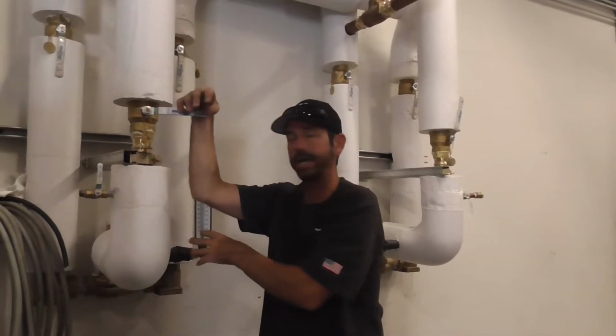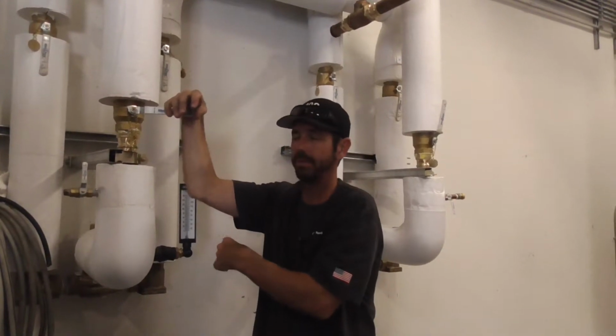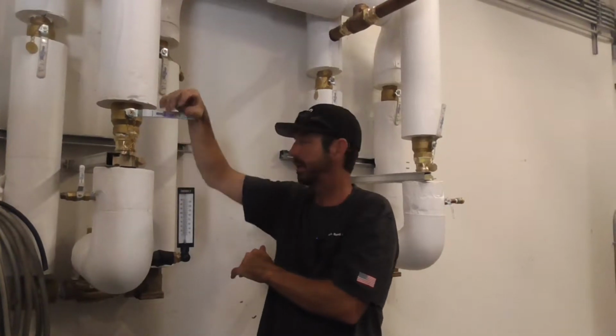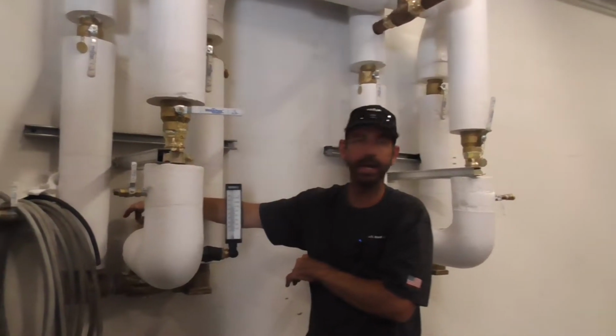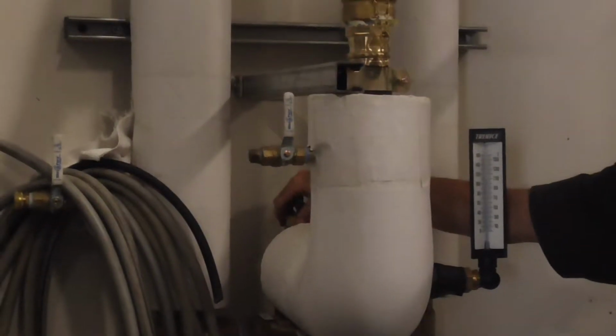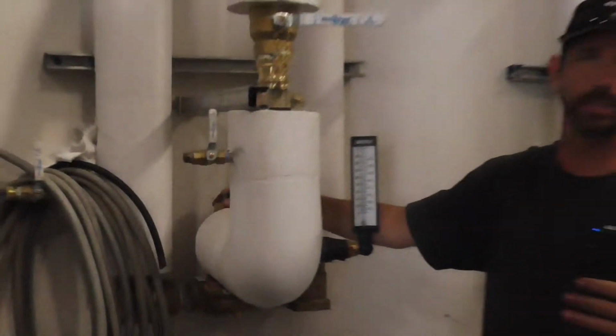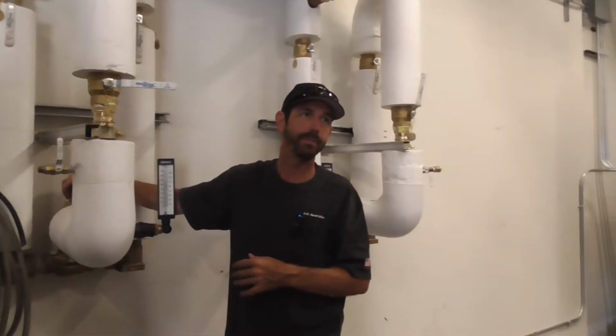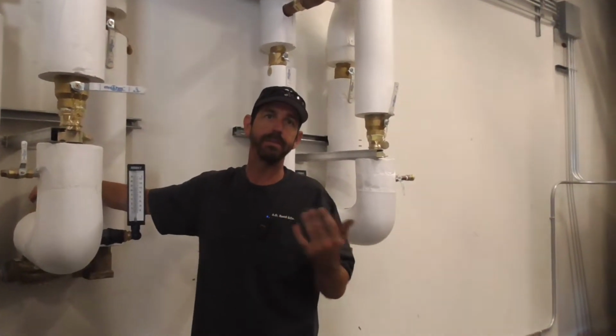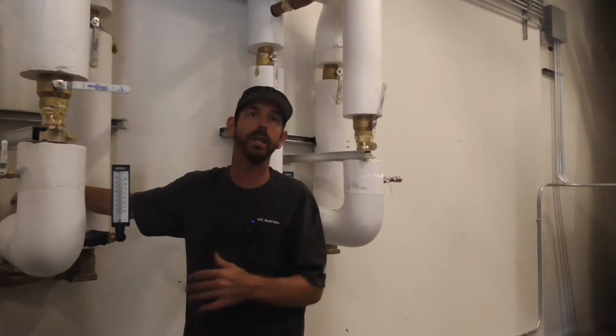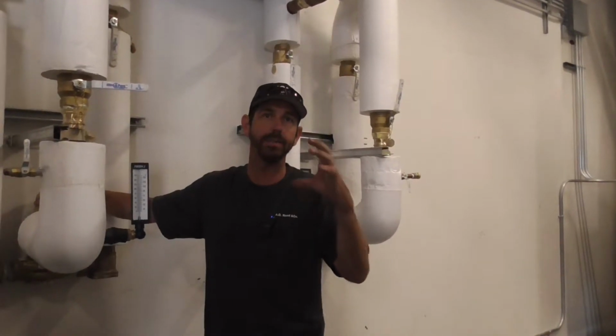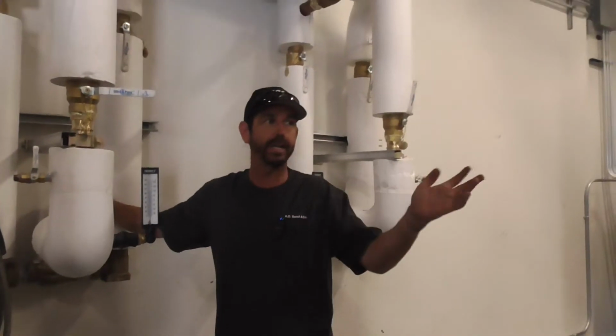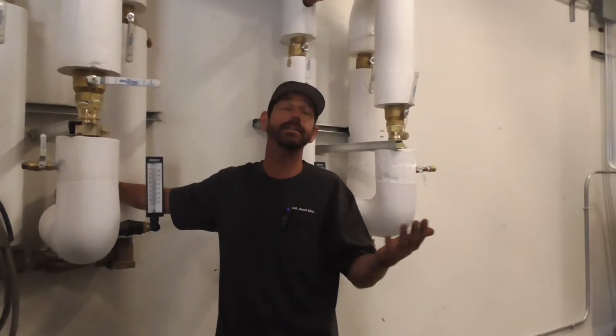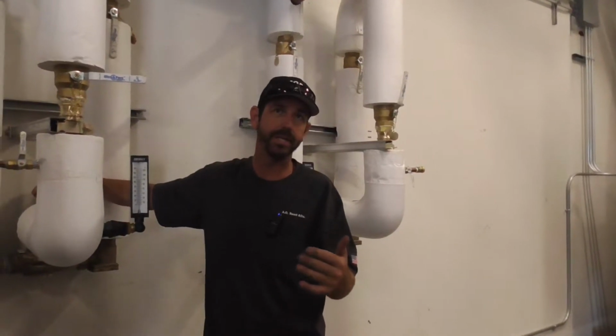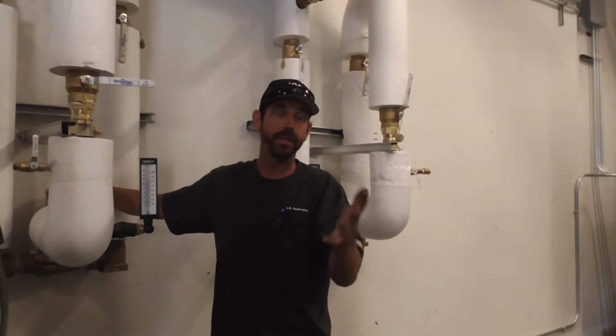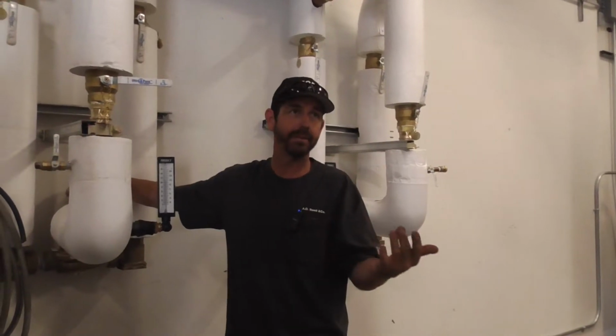We want to follow the manufacturer's guidelines on GPM. I believe it's 15, but the model number of the unit is on top of this nut right here, we can search for that information or use the O&M manuals that are turned over to search for that. Probably going to be easier to look the information up on the internet. Just be very careful looking up information on the internet. There's a lot of information. You just want to make sure you're on the right piece of equipment. And that would be true for any of the equipment anywhere. And anytime you try to use the internet to get your information, it's super easy to think you're in the right manual, but you're looking at a very similar manual for the same piece of equipment.